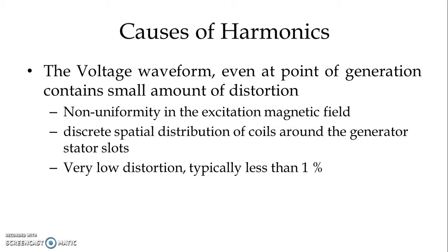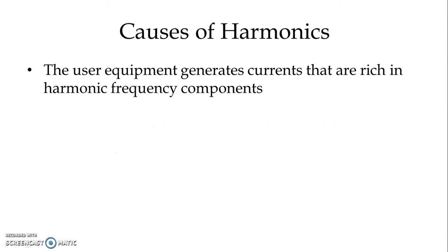The voltage waveform distortion at the point of generation is very low — typically less than 1%. Mainly, the harmonics or distortion is from the load side. The user equipment generates currents that are rich in harmonic frequency components, especially in very large commercial as well as industrial installations.